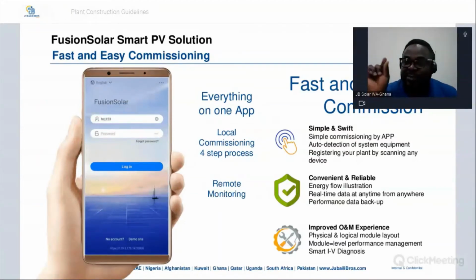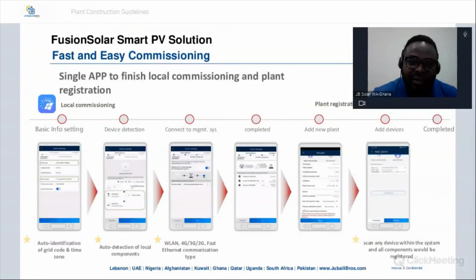Remember, the inverter comes with a USB adapter, as I showed you the first time. So you slot the USB adapter into the inverter, and then you look for its Wi-Fi, connect it to your phone, and then you are locally connected to the inverter. It will ask you to create an account, okay? So on the FusionSolar app, you create a username and then a password, and you are good to commission your system. Commissioning is also very simple. In fact, commissioning is just 4 steps. Just 4 steps, you can commission any inverter size that you want, and it's simple up to here. So as soon as you connect your system to the inverter locally, the inverter itself will open the app.